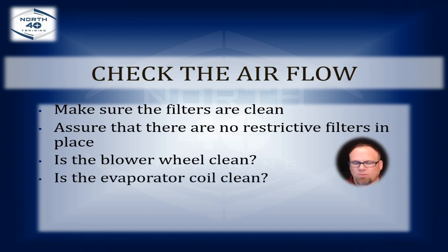Is the evaporator clean? We don't have as many evaporator issues now as what we used to because we have a secondary heat exchanger now that rests just above that blower. And so oftentimes the secondary heat exchanger is going to catch all of the junk that used to get caught in the evaporator coil. However, anything that gets past there that's a much smaller particulate, like dust and pet dander and things of that nature, are going to catch on a nice wet coil. So the evaporator coil can still get dirty.